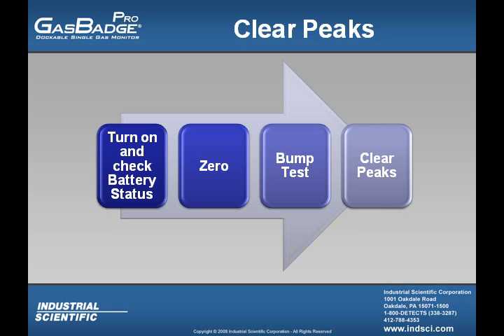And last but not least, the fourth step of operation, which is clearing the peaks. Clearing the peaks is important because the peak reading screen allows the user to see the highest concentration of toxic gases if a toxic sensor is installed, and the lowest concentration of oxygen if an oxygen sensor is installed. Those peak readings will stay in the instrument until the user clears them. The peak readings are stored in what we call non-volatile memory. What that means is that by just turning the GasBadge Pro off and back on again, the peak readings are still stored in the instrument. Even taking the battery out and putting it back in will not clear the peak readings. It reminds me of a black box in an airplane.